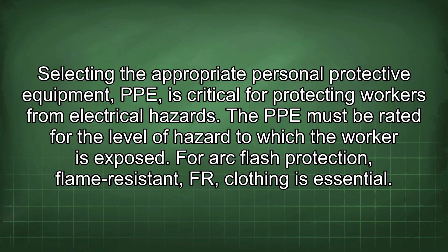Selecting the appropriate personal protective equipment (PPE) is critical for protecting workers from electrical hazards. The PPE must be rated for the level of hazard to which the worker is exposed. For arc flash protection, flame-resistant (FR) clothing is essential. The FR clothing must be rated for the incident energy level determined by the arc flash hazard analysis. Other PPE for arc flash protection includes face shields, safety glasses, and gloves.